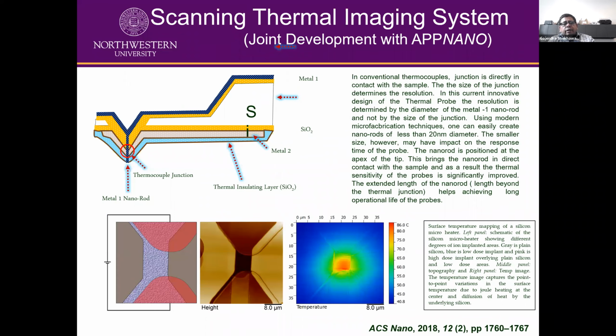Then I will move on to another functional AFM, which is high resolution thermal imaging. I developed this with a Bay Area company, App Nano. If you have seen the literature, conventional thermocouple based scanning thermal imaging systems are not very high resolution, about 200 to 300 nanometers. The thermocouple is in direct contact with the samples, and also takes up lateral heat and everything, which degrades the resolution.